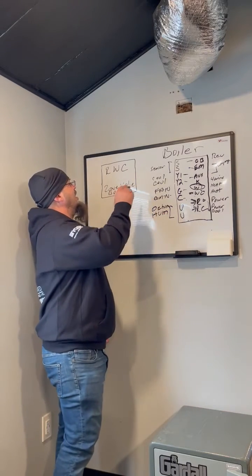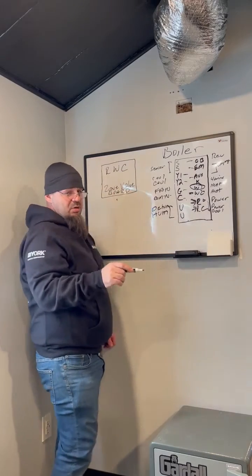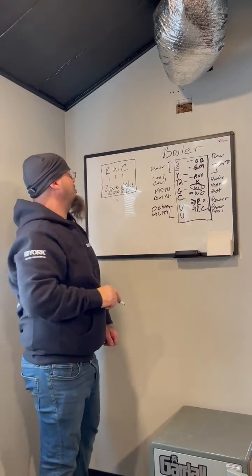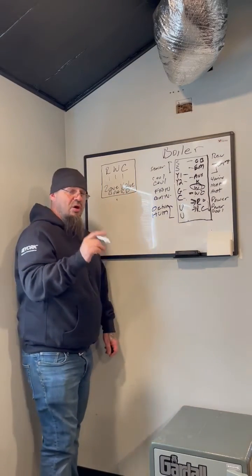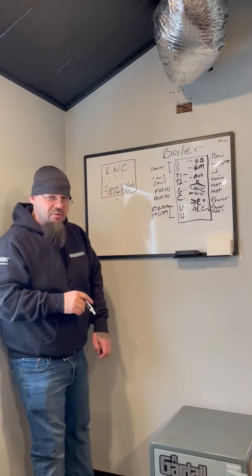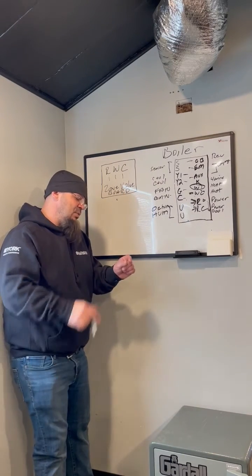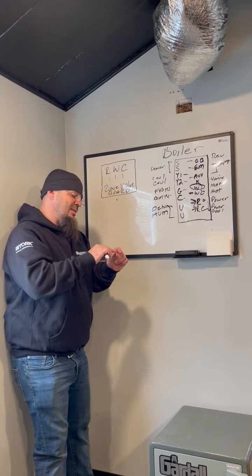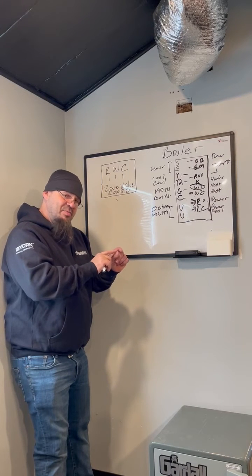One way that it can be done is sometimes you'll have a zone valve board on a multi-zone boiler, and those actually allow for power stealing thermostats. You'll see RWC right in the board, okay? Those often do have 3 wires going to the thermostat. When you pull it off there, I want you to grab the inside where the brown wire is and see if one of the conductors is wrapped back, because 2 are going to be tied into the thermostat, and there'll be 1 still left back wrapped in there.